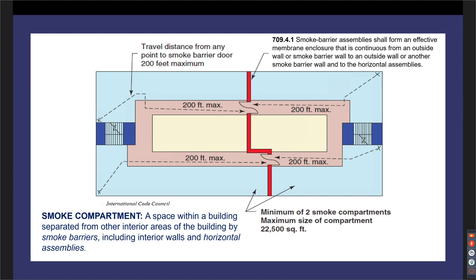And the definition in Chapter 2 for smoke compartment has changed in the 2022 code. It's a space within a building separated from other interior areas of the building by smoke barriers, including interior walls and horizontal assemblies. So your smoke compartment has the top, the bottom, and all the sides. Some forget that and think it's just about the walls. So top, bottom, you're creating the whole compartment, this box, and that's all protected with smoke barrier. I say that because the penetrations, and the requirements for that, will be different.